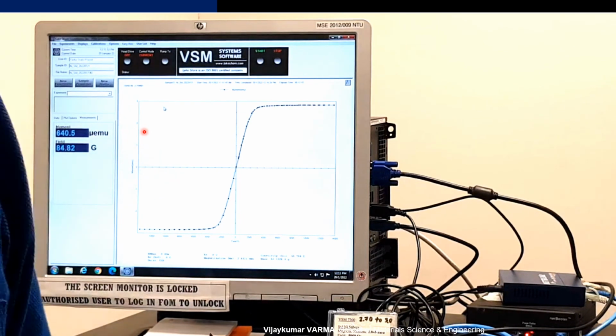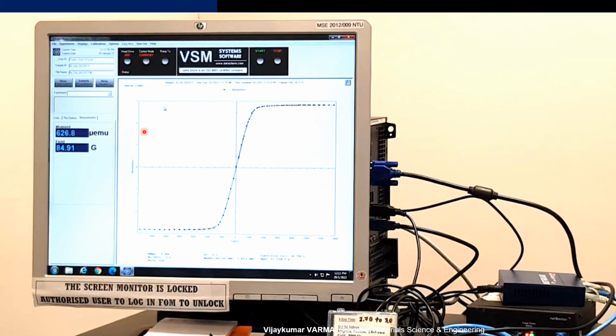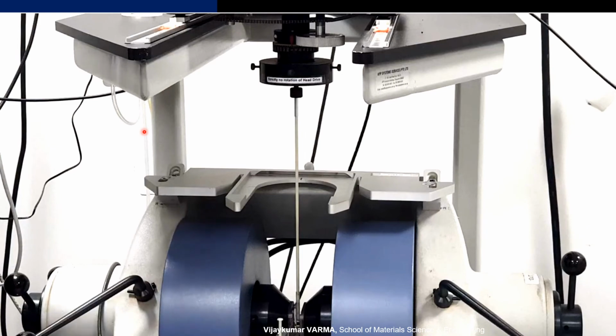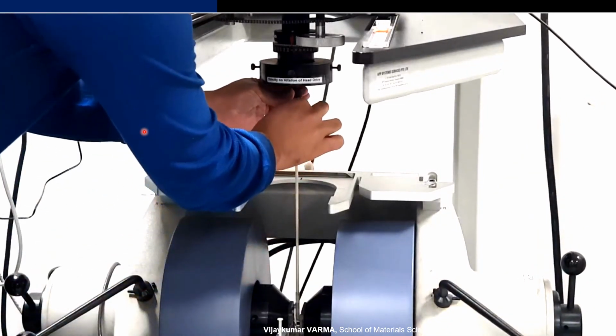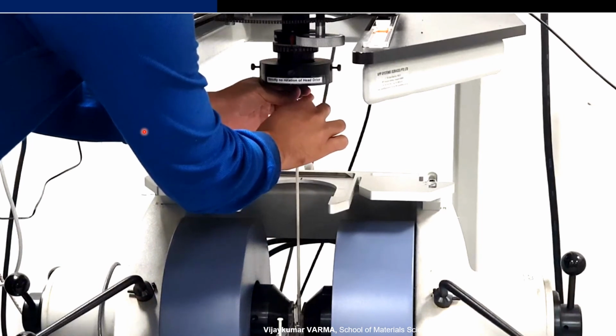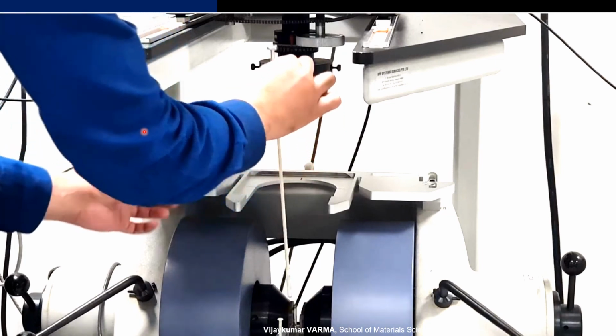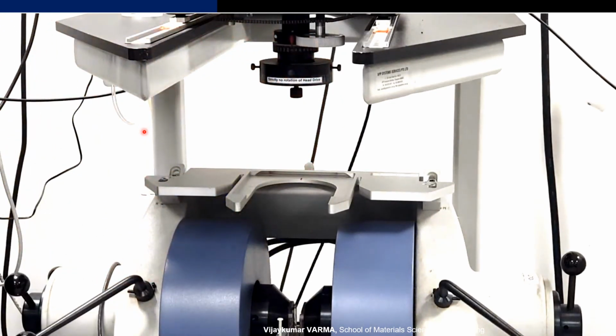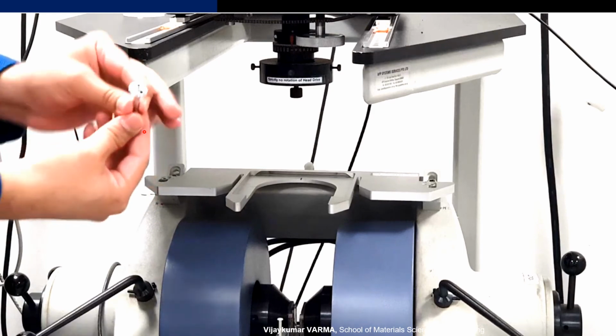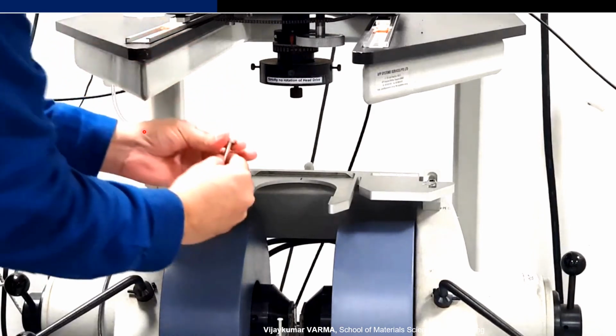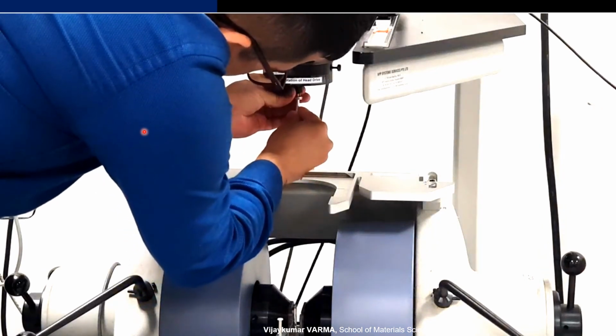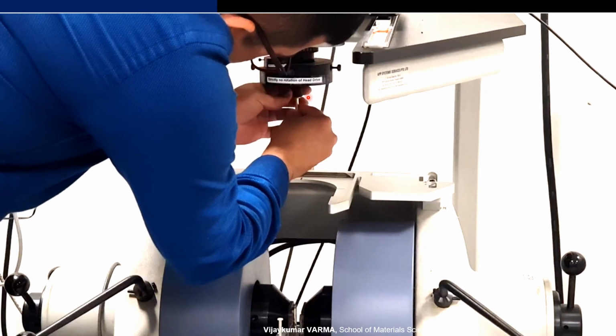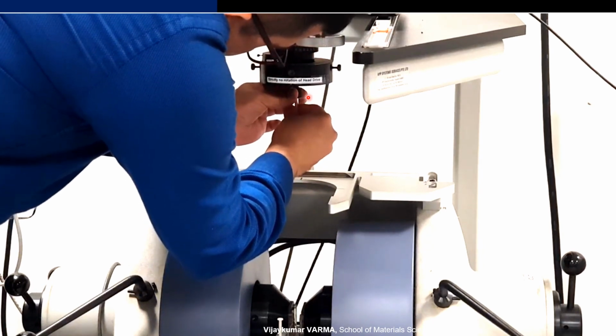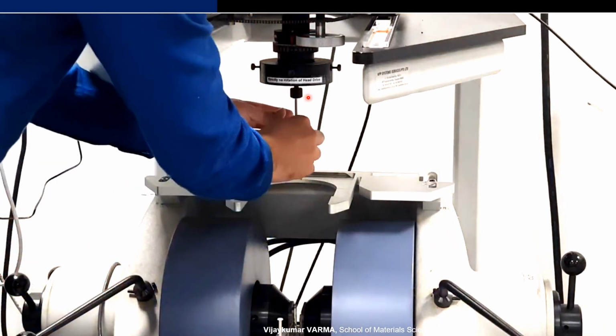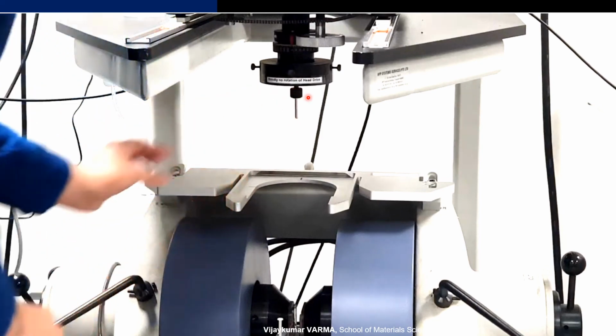Once the head drive is off, we can move to the next step, which is removing the sample from the VSM. Carefully rotating in a clockwise direction to remove the sample holder and mounting the blank in the head drive. Like the earlier step, align along the cavity. You see a small stud to align, and then rotate the screw to fix it. Once we did that, we need to turn on the head drive again.